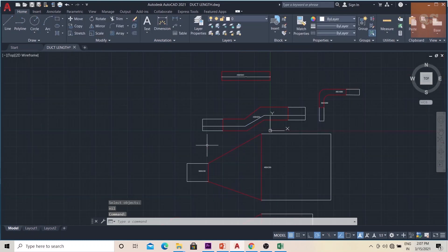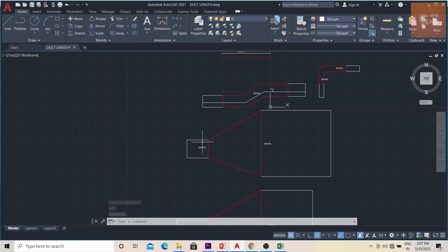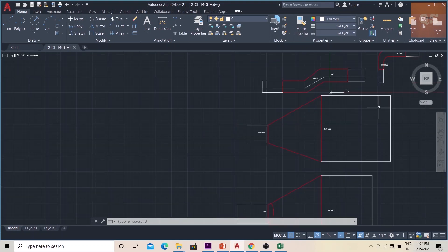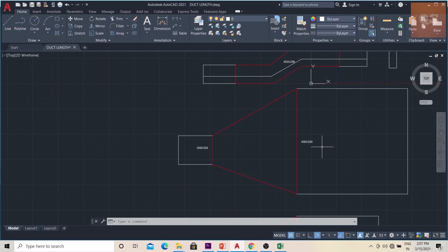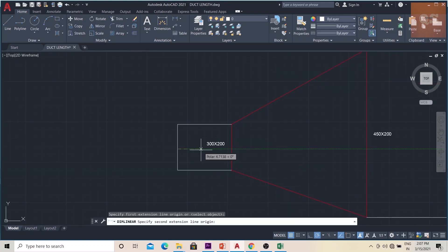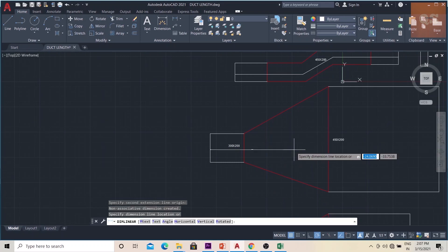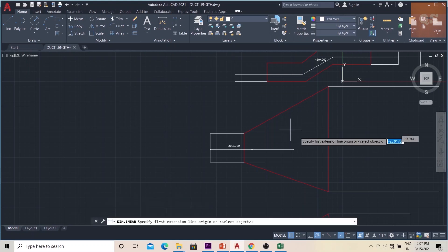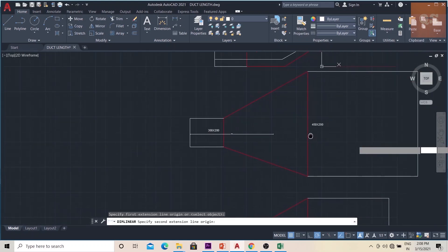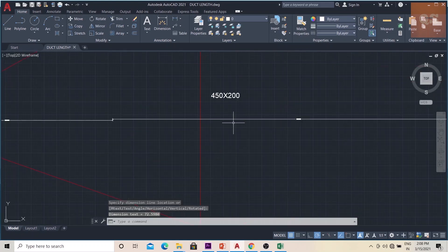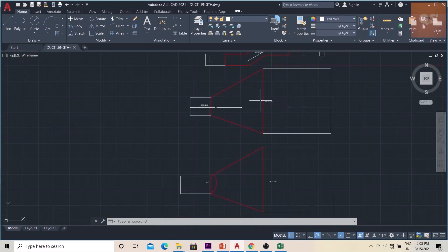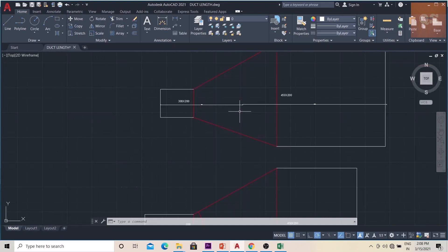Now this is a reducer. There is one duct coming 300x200 and it is connected to another piece of duct, 450x200. In this scenario, this part will be till the center part of this piece — this will be the length for 300x200, and the remaining will be from the center part onwards, which will be the length for the 450x200 piece. This is how you measure the length throughout the fittings, through the center of the duct and over the center part of the fitting.